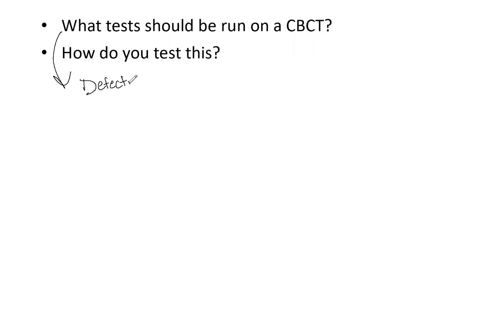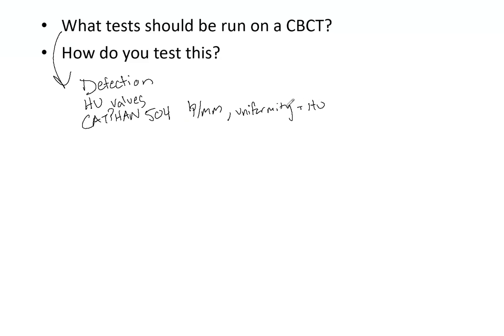Ideally, you have done them and can talk about real hands-on experience from your clinic. First, of course, detection — if something bumps that detector on the cone beam CT, it needs to throw a fault and stop its motion. You then have your HU values; whether you use offline adaptive radiation therapy or not, you need to verify HU values are correct. There's also a Catphan phantom that you should be familiar with — it will allow you to verify the resolution, specifically line pairs per millimeter, and also helps you check uniformity and HU values.